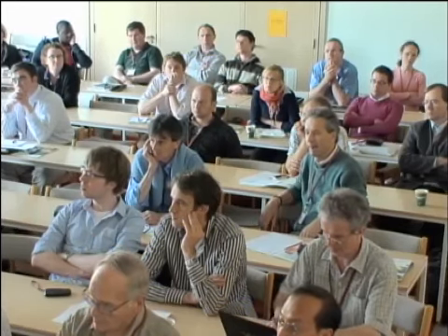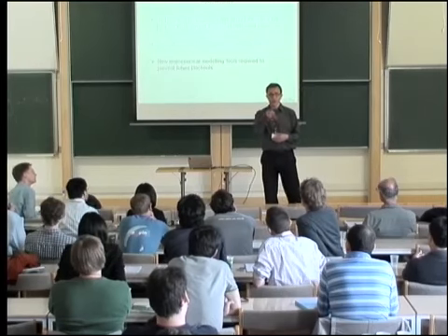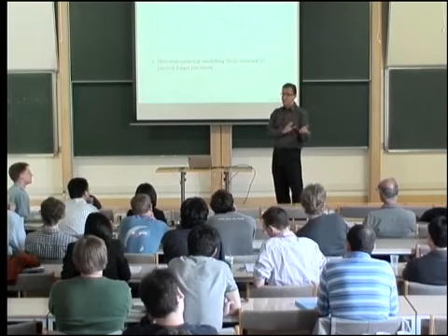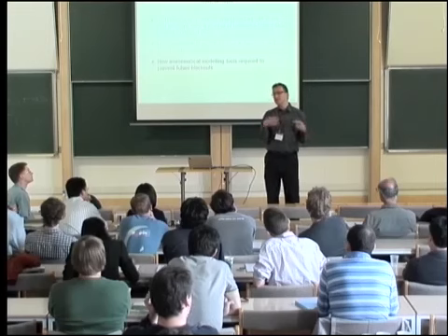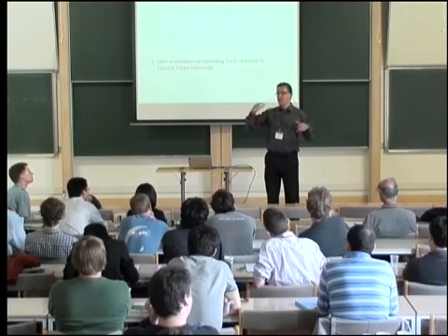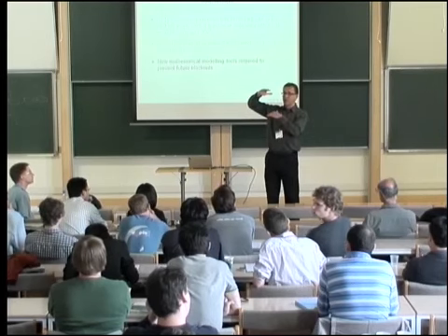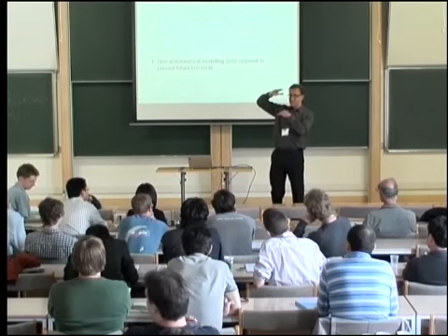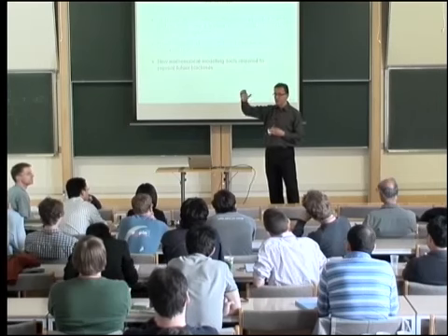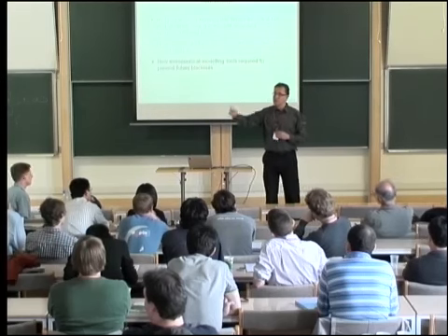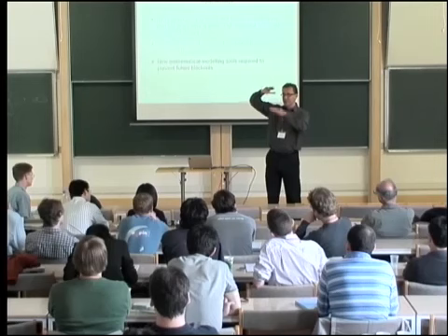Well, there are voltage regulators as well — I didn't mention that. The presentation before lunch was about voltage regulators, designed in a similar manner to keep the voltage stable in the system, within the capabilities of the power station's so-called exciter. So the voltage is kept constant through a feedback mechanism. When the voltage drops, the generator's voltage controller tries to keep the voltage up to a level, until it hits a limit — and then it cannot keep it up anymore.